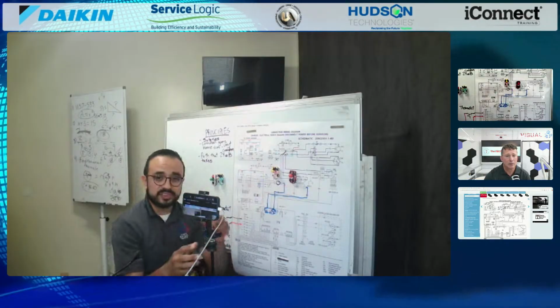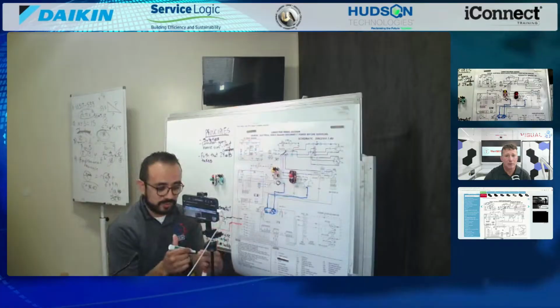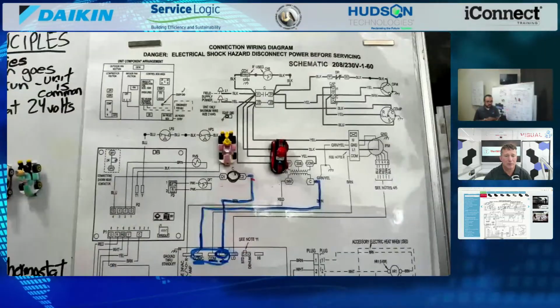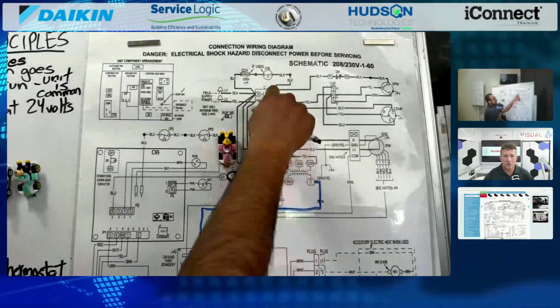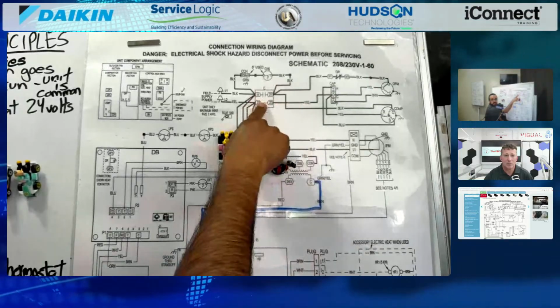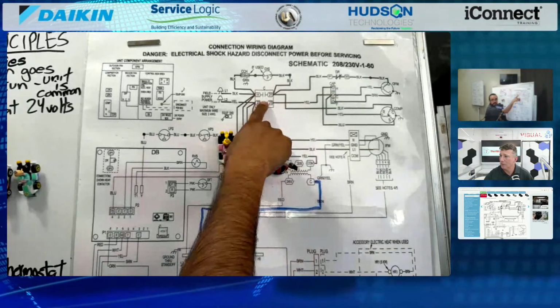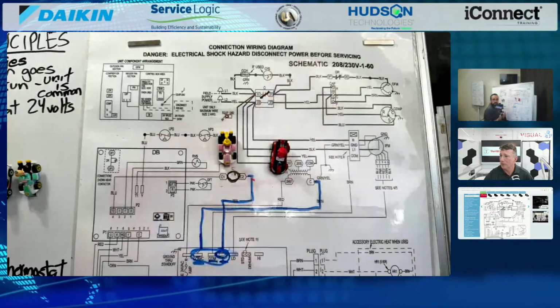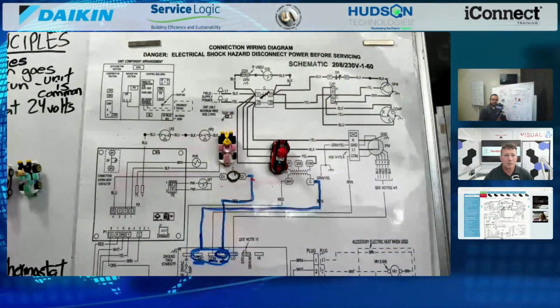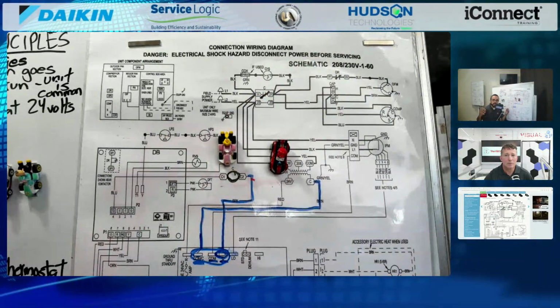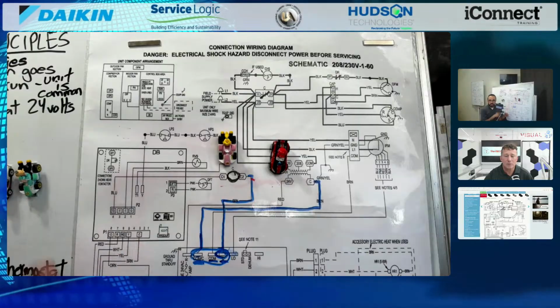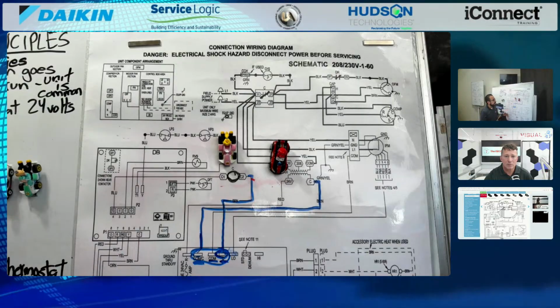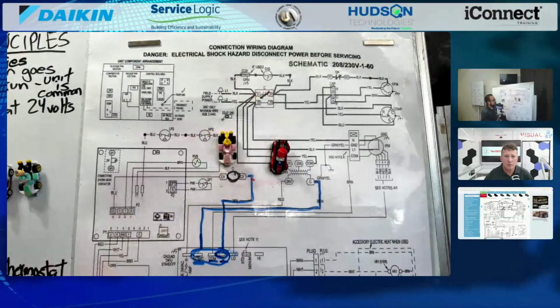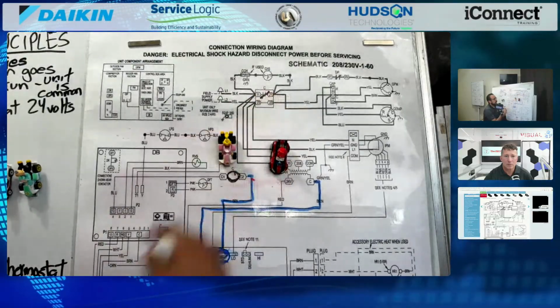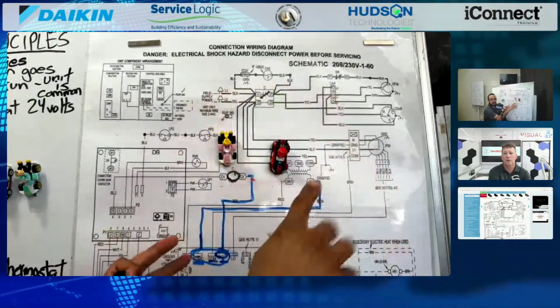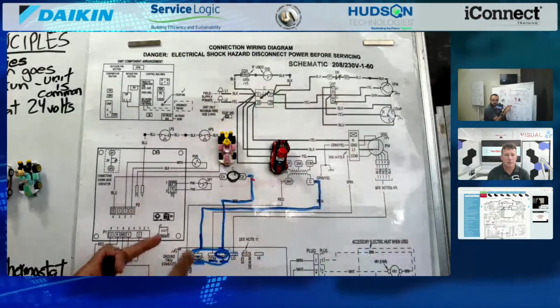It's interesting, because all we really care about is this contactor here, where you see it's open. All we care about is for that to close, because if it closes, then stuff turns on and you get some cooling or heating. This is a heat pump, so it would be heating in this case. All we care about is for that switch to close. How do we close that little switch so power can go and turn stuff on? Well, we've got to power up the contactor coil.